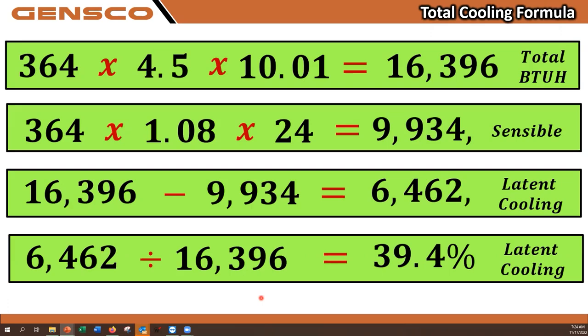This is the actual cooling BTUs that's going to drop the temperature in the room. But the amount of cooling that's actually removing moisture is going to be the difference between the 16,396 and the 9,934. So if I subtract 9,934 from 16,396, I end up with 6,462 BTUs of latent cooling. This is the amount of BTUs that's actually removing moisture. And if I take that number, 6,462, and I divide it by the 16,396 total cooling, it tells me that my latent cooling percentage is 39%.